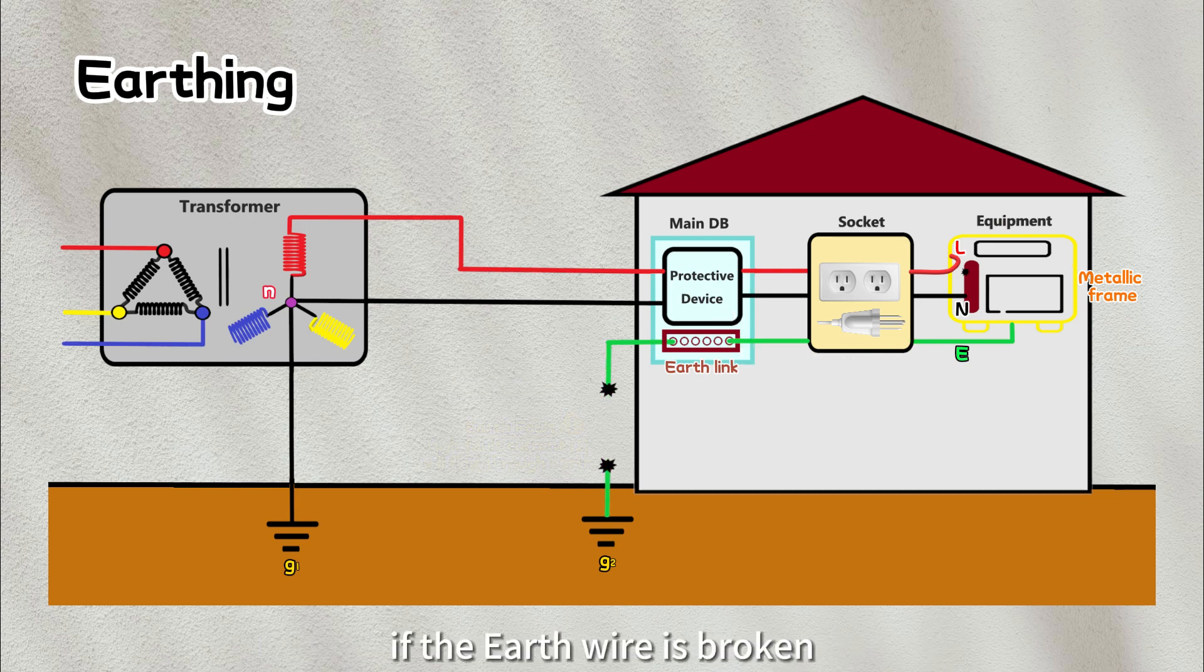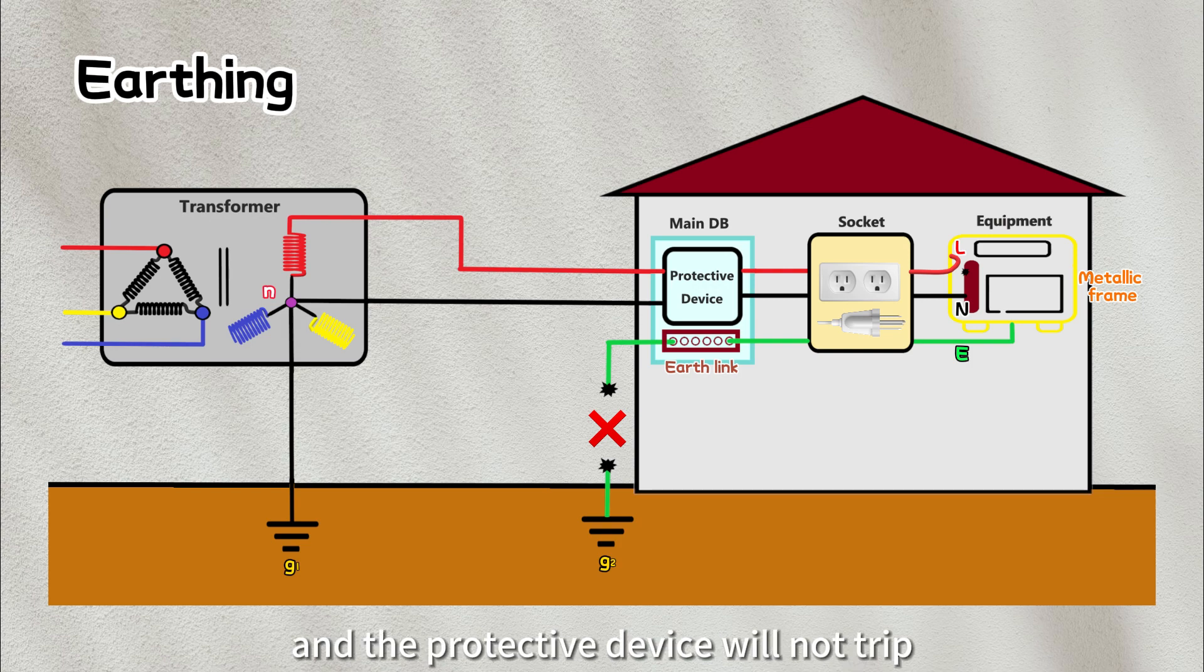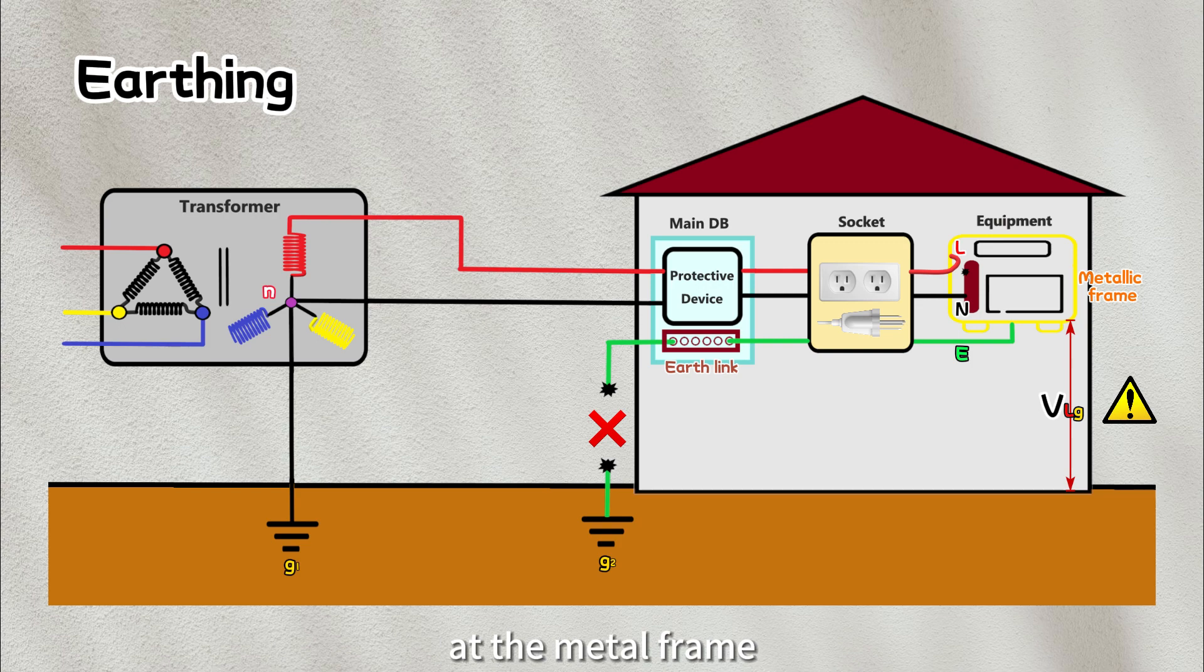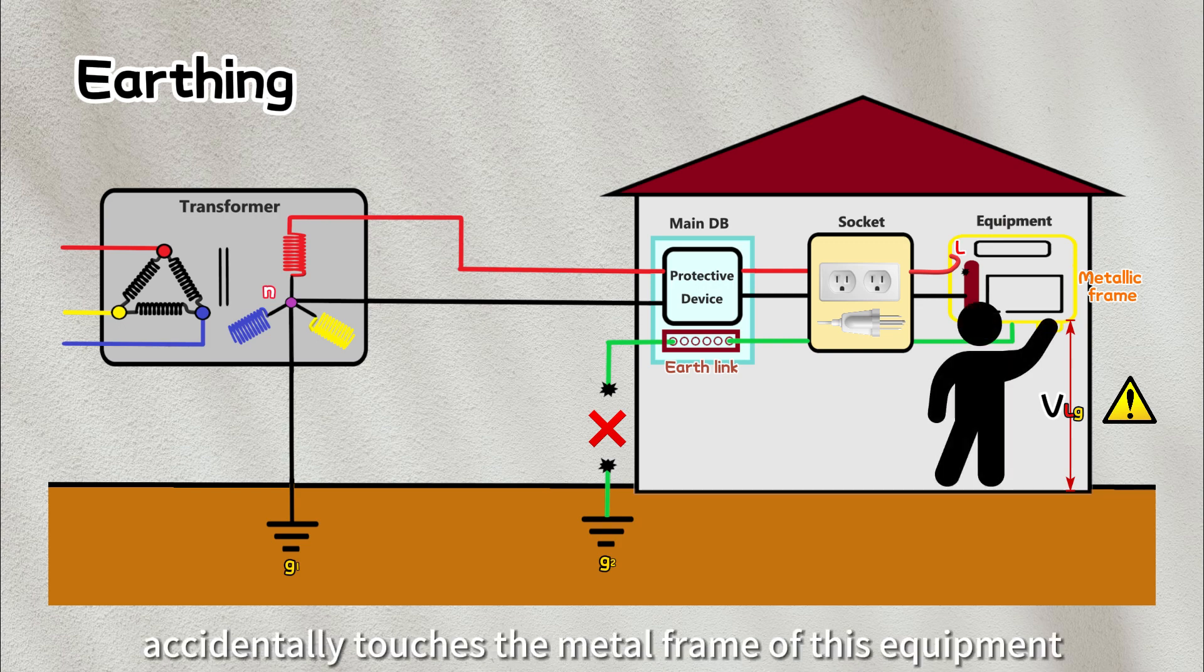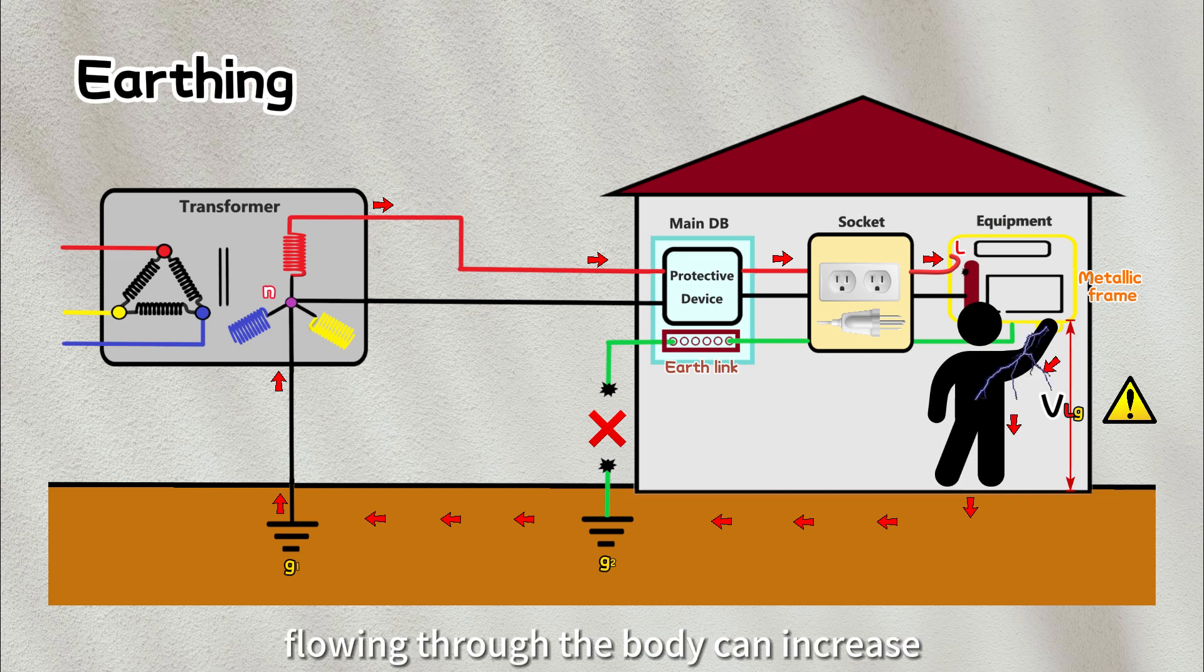Let's observe what will happen if the earth wire is broken. Now if the live wire touches the metal frame, the loop is not complete. There will be no current flowing and the protective device will not trip. In this case, there will be a dangerous voltage at the metal frame remain unnoticed. When a person accidentally touches the metal frame of this equipment, the person will be completing the loop through ground back to the transformer source. Consequently, the fault current flowing through the body can increase risk of electrocution. Therefore, it is important to ensure a proper connection of earth wire to ground.